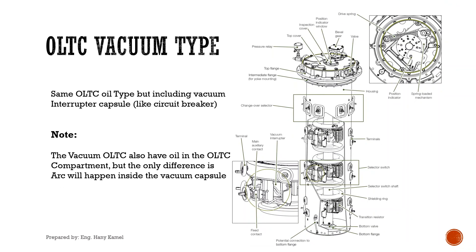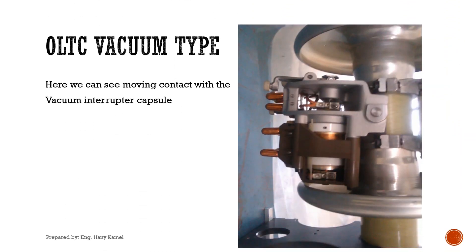OLTC vacuum type. As we can see in the picture, the OLTC vacuum type is the same as the OLTC oil type, but includes a vacuum interrupter capsule like a vacuum circuit breaker. Very important note: the vacuum OLTC also has oil in the OLTC compartment, but the only difference is that the arc will happen inside the vacuum capsule. In this picture we can see the moving contacts and the vacuum interrupter capsule — the white color part.